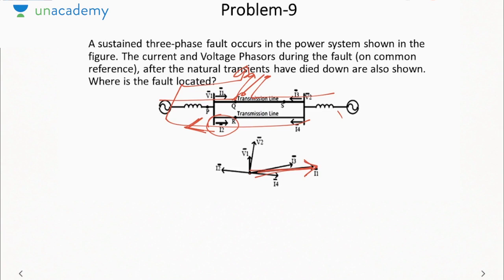Because the nearer the fault to a bus, the lesser the impedance and higher will be the fault current. So highest fault current has the fault nearest to the bus. So nearest to the bus V1 or 1 is point Q. So answer should be Q.